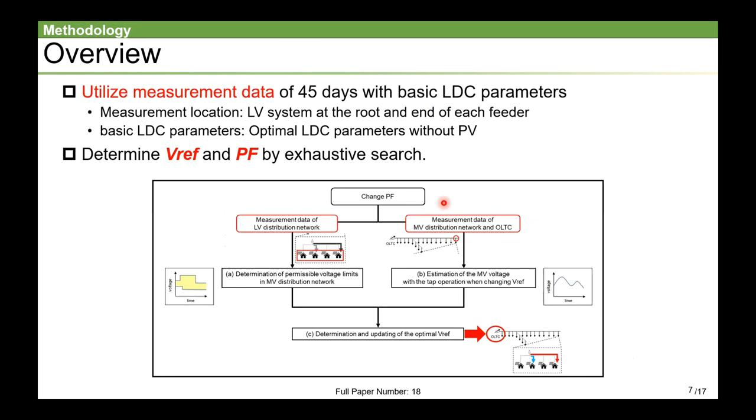The proposed method is described from here. This method utilizes voltage measurement of 45 days when OLTC is operated with the basic parameter, and the power factor is changed to some value after PV penetration. Here, the basic parameter is the optimal parameter when PV is not deployed. In addition, we choose every customer at the root end of each feeder as the measurement locations. Look at this figure. The proposal method consists of three main steps.